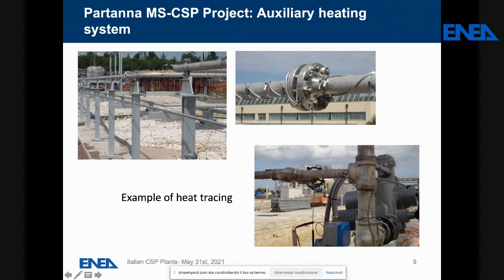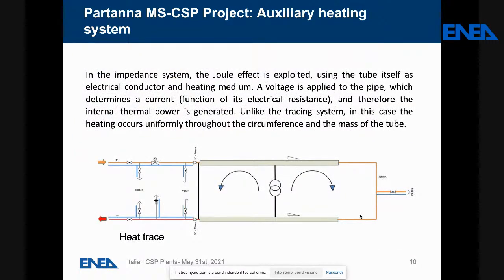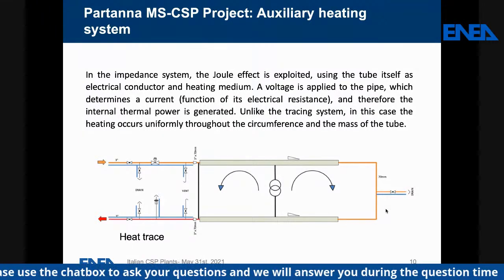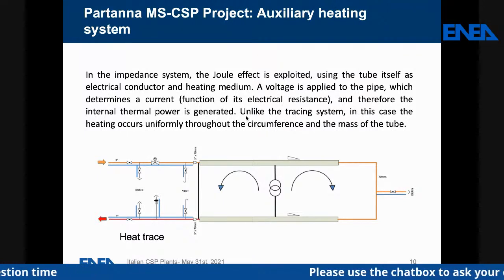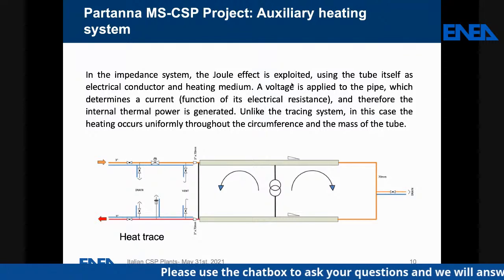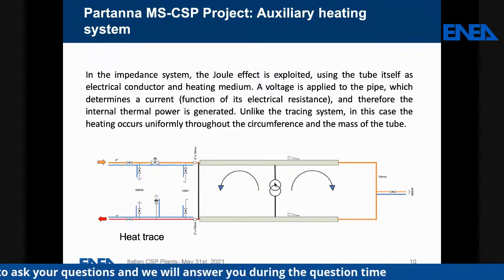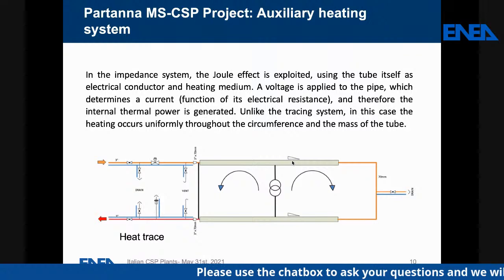Here we can see some examples of heat tracing. Here on the piping, on the flange, on the valves. Instead, for the impedance system, the Joule effect is exploited, using the tube itself, the receiver tube, as electrical conductor and heating medium. So a voltage is applied on the tube, normally in the middle of the electrical circuit, so in this point. This voltage determines a current, and the thermal power is generated. In this case, the heating of the system occurs uniformly through the circumference and the mass of the tube.